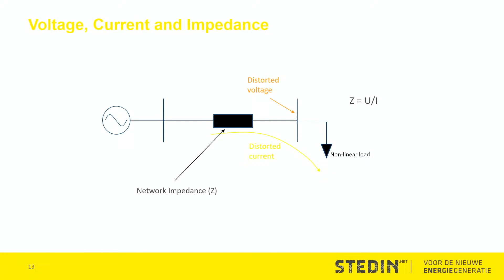Now, power quality - the word power is a combination of voltage and current, and if you take the ratio of voltage to current, you get impedance. So power quality is about voltage, current, and impedance - that's Ohm's law, not that fascinating, but interesting to understand this basic concept. The network impedance and voltage is what the grid operator is responsible for, and on the other side are the manufacturers of equipment - they put load on the network that draws a certain current, and this current, in combination with the impedance, will disturb the voltage. So power quality is always about voltage and current and the interaction between both.